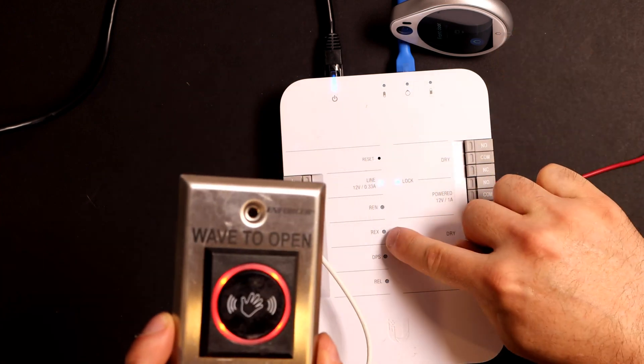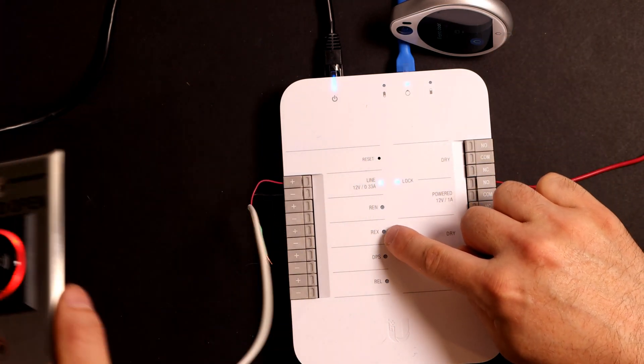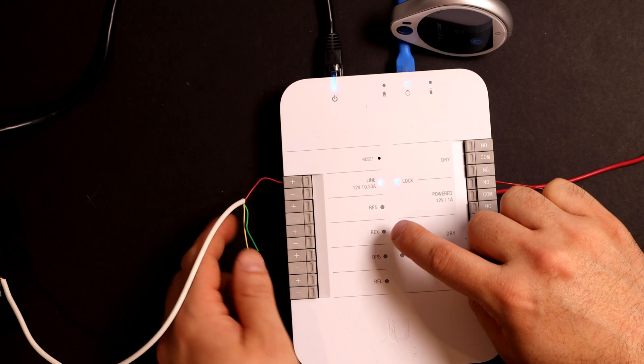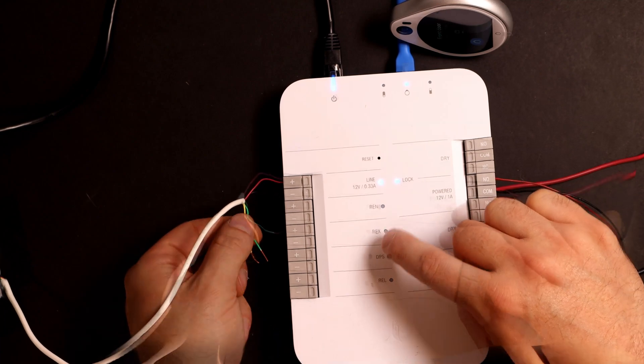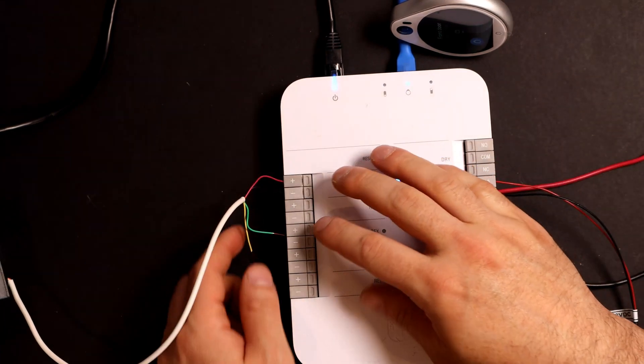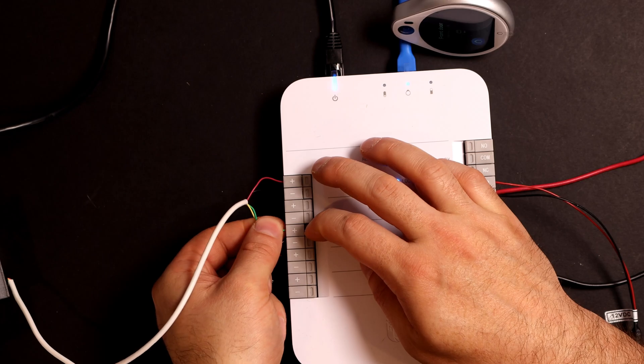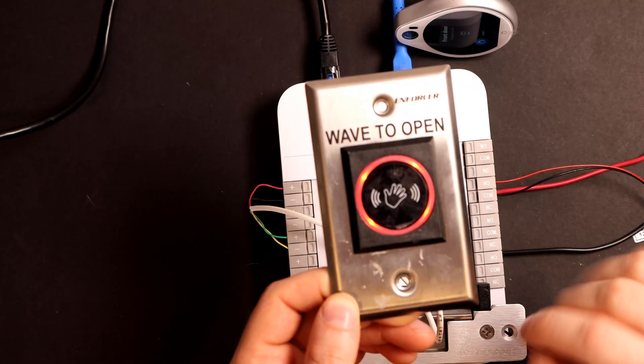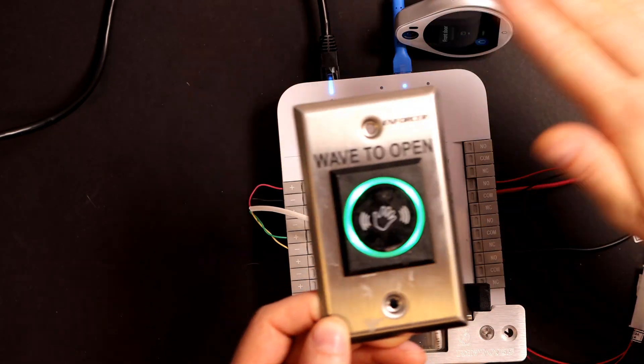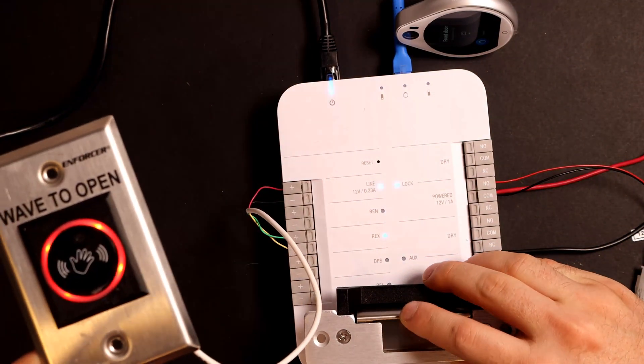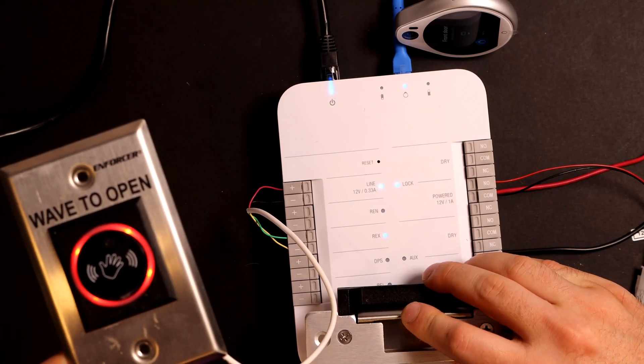But it won't do anything, because we don't have it in the request to exit. So we need to connect that now. So I have my green and yellow, and this is just four conductor station wire. So let's put that into the request to exit. Now, if we wave our hand in front of it, it will go green and the strike will unlock. It will lock after a few seconds.